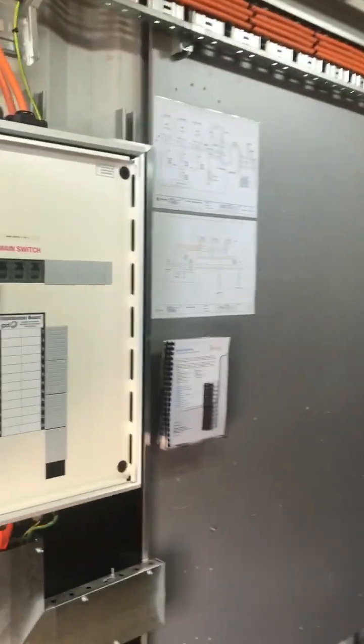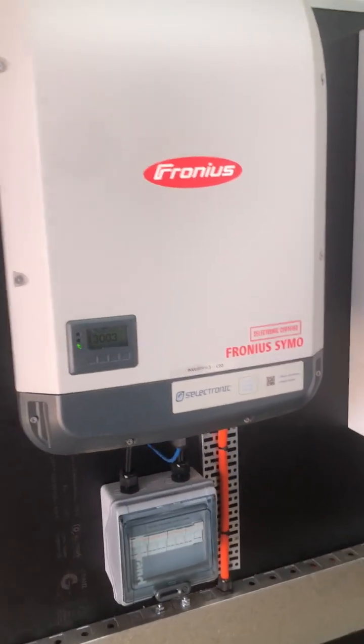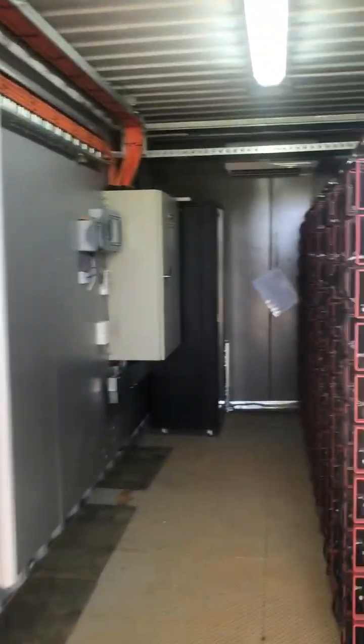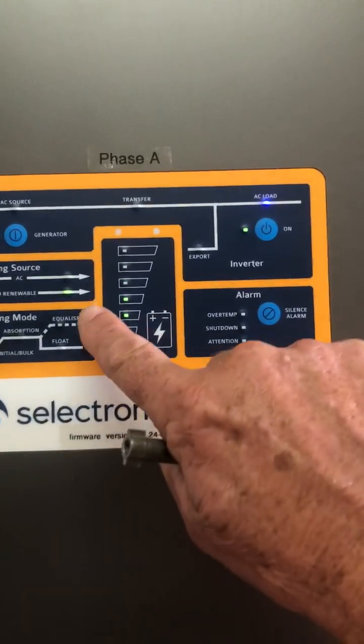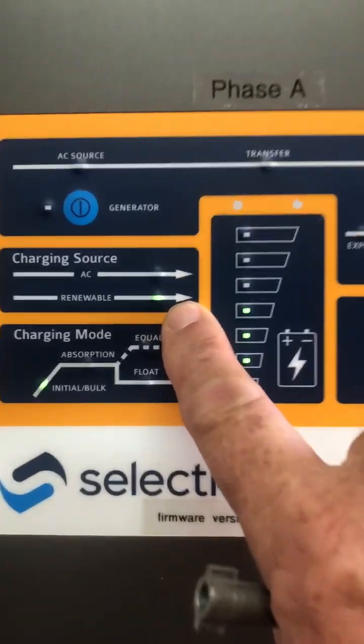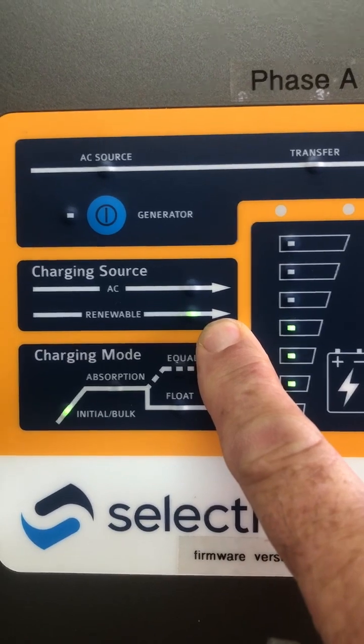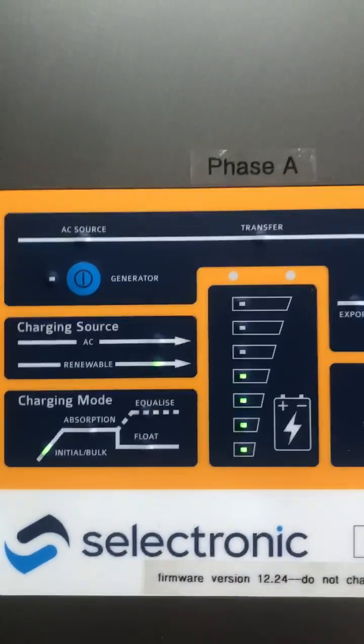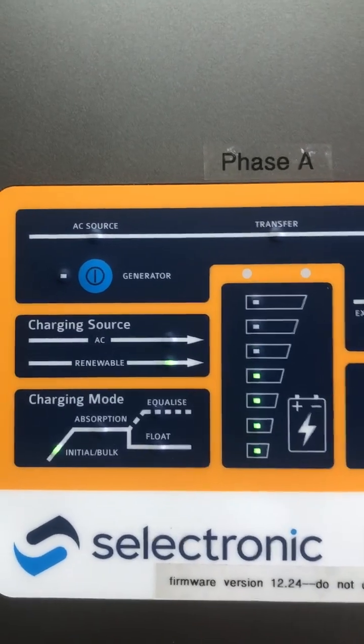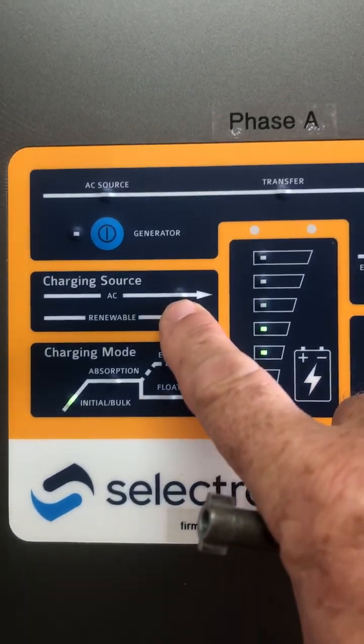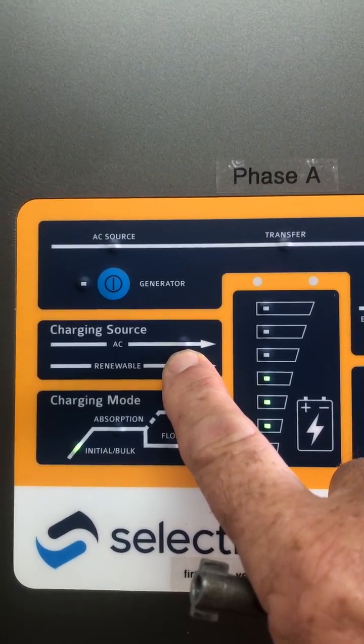So all the energy at the moment, you could probably actually hear these Phoenix inverters working. It's only early morning here, but already on one of them we have 12 kilowatts, 14 kilowatts, and 13 kilowatts. So they're already putting quite a bit of energy out, supporting the site load and simultaneously charging the batteries. And I know they're charging the batteries because if I look here on the front face of the inverter, I can see that the charging source is the renewable energy source. If the generator was operating because it was a cloudy day or we needed additional energy, then we would see a little light on here, which would be the charging source, which would be the AC side.